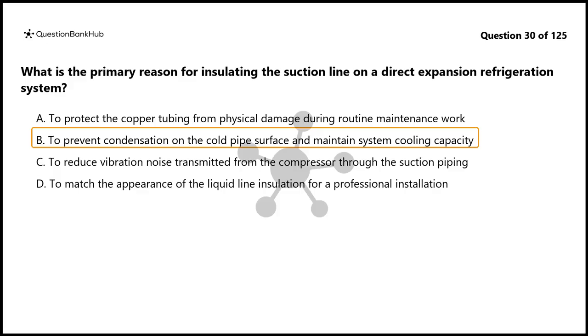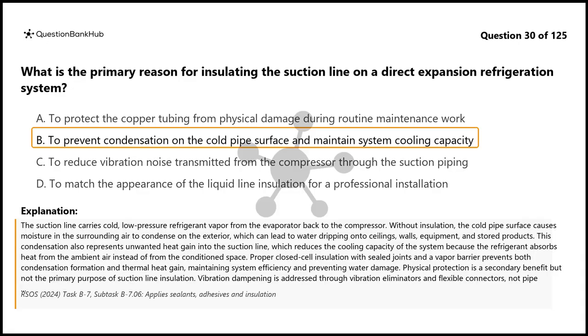The correct answer is B. The suction line carries cold, low-pressure refrigerant vapor from the evaporator back to the compressor. Without insulation, the cold pipe surface causes moisture in the surrounding air to condense on the exterior, which can lead to water dripping onto ceilings, walls, equipment, and stored products. This condensation also represents unwanted heat gain into the suction line, which reduces the cooling capacity of the system because the refrigerant absorbs heat from the ambient air instead of from the conditioned space.